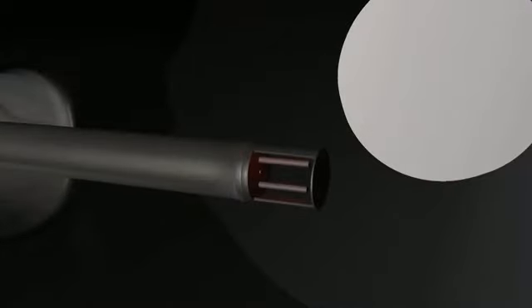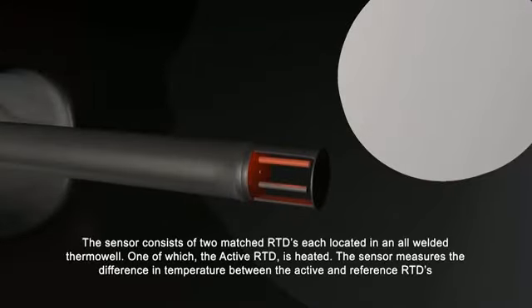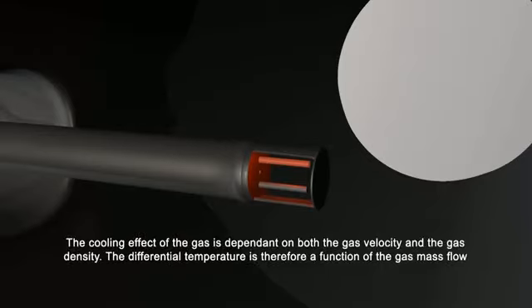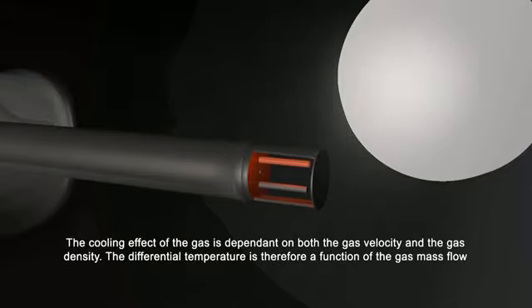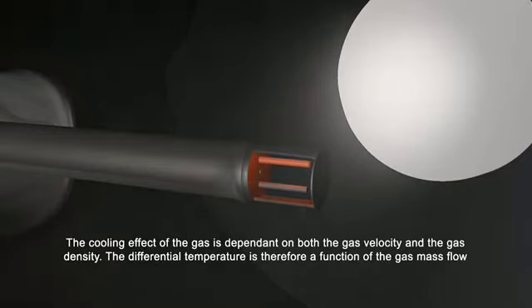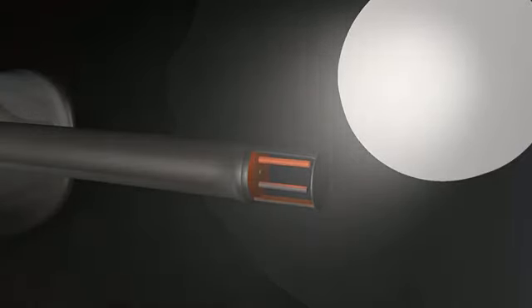The sensor consists of two matched RTDs, each located in an all-welded thermowell, one of which, the active RTD, is heated. The sensor measures the difference in temperature between the active and reference RTDs. The cooling effect of the gas is dependent on both the gas velocity and the gas density. The differential temperature is therefore a function of the gas mass flow. The temperature of the gas is also monitored and used in the mass flow equation.